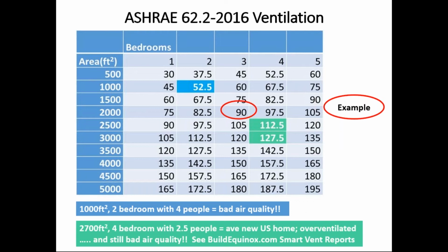Now the ASHRAE 62.2 ventilation schedule, the most current one, 2016. Smart ventilation, covered by section 4.6 in 62.2, requires that the ventilation system results in no more exposure to indoor pollutants than what the ASHRAE ventilation standard would. Nominally, although it's not stated explicitly, this would be keeping the home at about 1,000 parts per million of CO2, which would be about 20 CFM per occupant. That's an occupant at a sedentary level: sitting, reading a book, office work type activity.